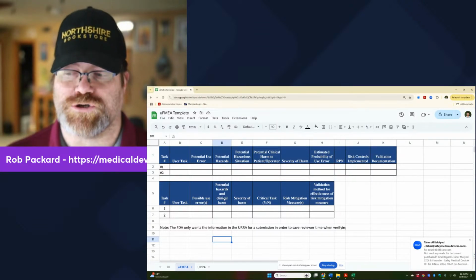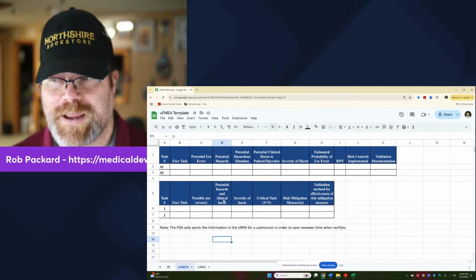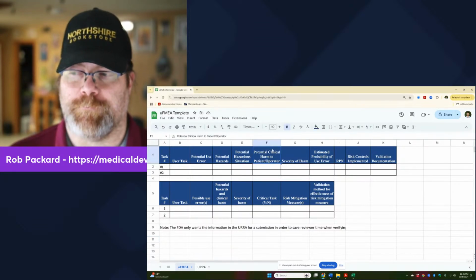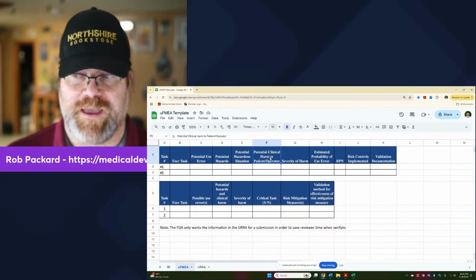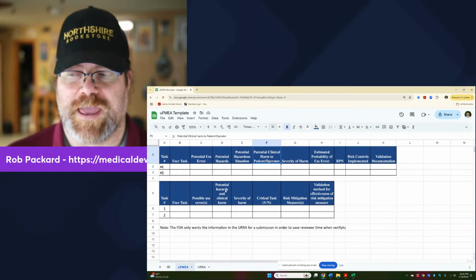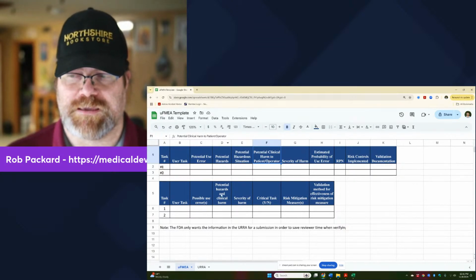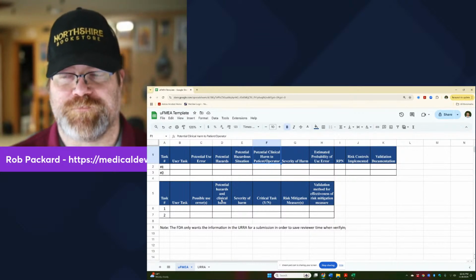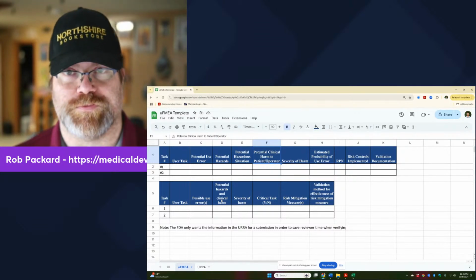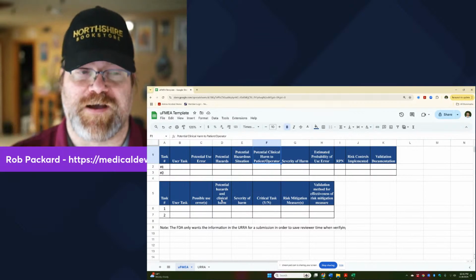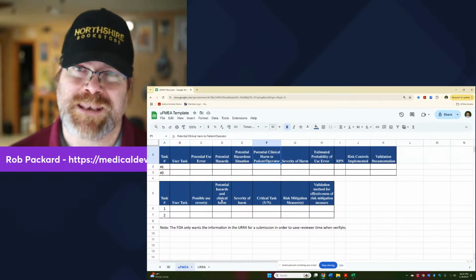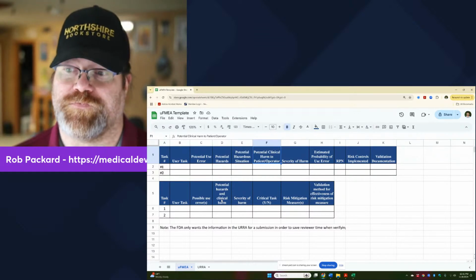Potential hazards and clinical harm. So you might have some clinical harm that you have to add. You'll notice in column F of the uFMEA, we have some harms. So you might have some information in F that you need to add to this column. But hopefully D in both of them matches up. You might have a little bit of information from F that you have to manually add. So there might be some manual work there. And if you have a 500-line uFMEA, that could take you quite a while. If you have a 10-line uFMEA, you probably don't have enough use errors identified yet.